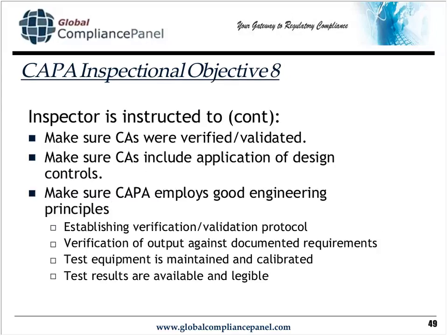They're also going to look to see if you've included design controls in your verification or validation. Because even though there are subsystems, there's quite a bit of crossover between subsystems. So the inspector isn't going to ignore design controls when they're looking at your verification or validation of your corrective action. And they're going to look to see if you've implemented good engineering principles.